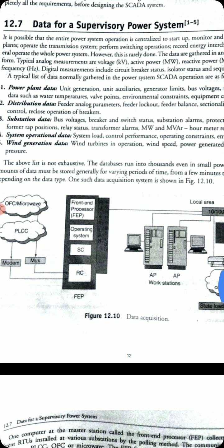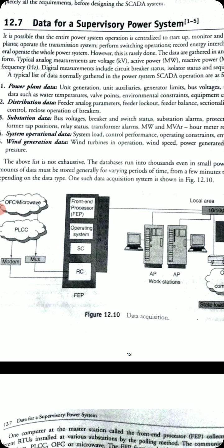Which is then displayed on the single line diagrams, which helps the user to get the data from the human machine interface. So the front end processor handles normal functions like converting the RTU formats into the host format, because the RTU's format is different, the host format is different. So it is converting the RTU format to host format, and allowing smart scanning of pre-selected RTU measurements, then providing exception reporting, reducing the CPU interrupt loading.